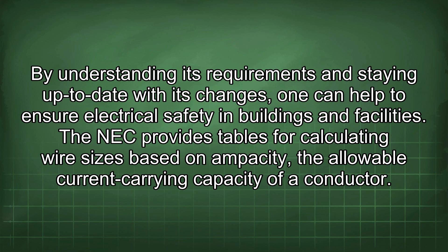Secondly, the NEC is a valuable resource for electrical professionals. By understanding its requirements and staying up to date with its changes, one can help to ensure electrical safety in buildings and facilities. The NEC provides tables for calculating wire sizes based on ampacity, the allowable current carrying capacity of a conductor. The ampacity of a wire is affected by several factors, including the wire's material, its size, its insulation type, and the ambient temperature.